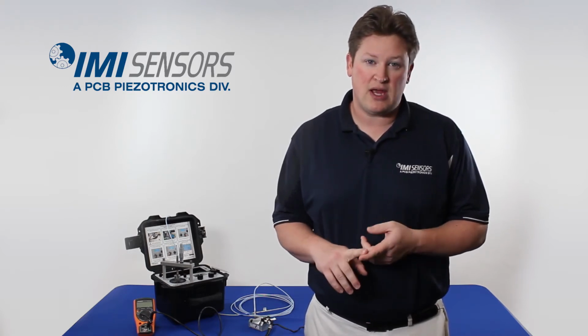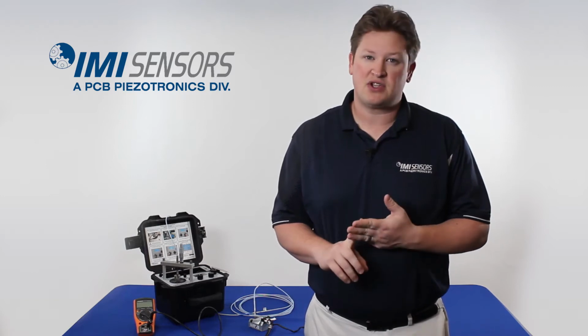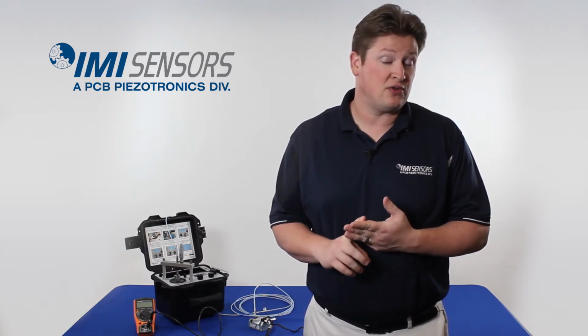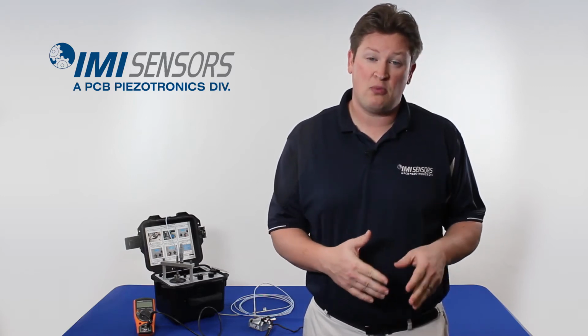So by doing a dynamic test where you actually simulate vibration at real machine running speed, not only can you create a calibration certificate, but at the same time you can make sure that the vibration alert triggers, the vibration shutdown triggers, and all of the shutdown logic triggers. You can test the whole system from the tip of the probe all the way to the shutdown logic, which gives a user terrific peace of mind.